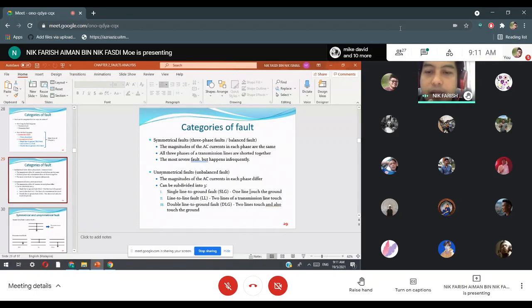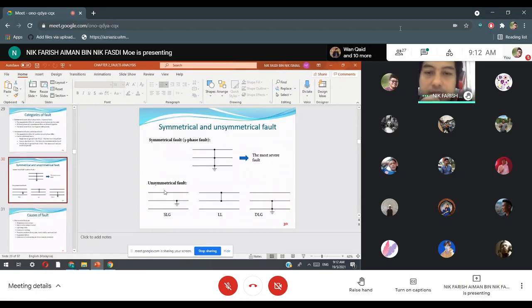Single line to ground fault - one line touches the ground, one line becomes equal to ground. Line to line fault - two lines shorted, meaning line A, B, C, maybe A and B are shorted. Double line to ground - two lines, say A and B, shorted and go to ground, touching ground. This happens if your isolation fails for any reason, it can damage the isolation causing it to short to ground. So here we have three phase fault, balanced fault, symmetrical fault, unsymmetrical fault. Alright.